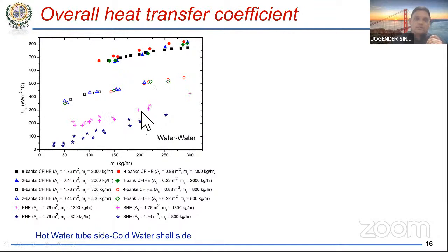So we can see a huge effect of the shell side flow rate on the performance of the coiled flow inverter heat exchanger, and in shell and tube, on the shell side flow rate. Basically, if we increase the shell side flow rate, we will see a drastic increase in the overall heat transfer coefficient of the coiled flow inverter. This is basically for all the 8, 4, 2 and 1 bank heat exchangers. That is for 800 kg per hour of shell side flow rate. This is for 2000 kg per hour of shell side, and you can see that it is more than a twofold increase in the overall heat transfer coefficient with the increase in the shell side flow rate.